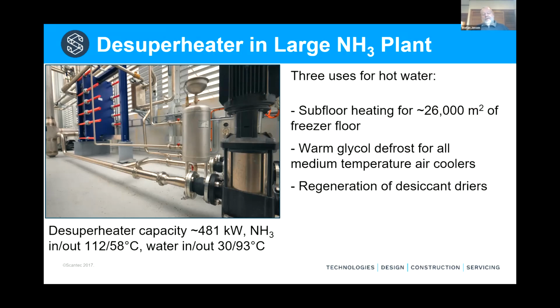And this is significant. In a 40 to 50,000 cubic metre cold store, an electrically regenerated desiccant dryer can consume up to 10% of the electricity consumption of the refrigeration plant that runs that cold store. So this is quite significant. I mean, a typical 40,000 cubic metre cold store with a low charge ammonia plant will take around 1,200 megawatt hours a year. 10% of that is very significant.